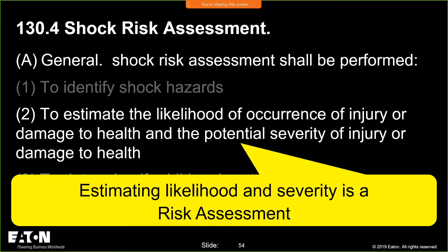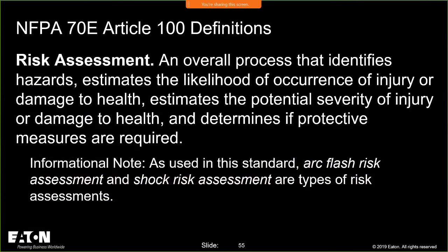A lot of people get the terms severity, likelihood, and elimination mixed up a little bit. But you have to establish and estimate the likelihood of occurrence that you're going to come in contact with these components. So you have to do a risk assessment, which basically estimates the likelihood of occurrence and injury, and the severity of that event. So you may say, I'm standing on a 2-foot step stool, and I could fall. I definitely could fall off of a 2-foot step stool. But the severity to me, if I fall off a 2-foot step stool, might not warrant putting on fall protection and doing all these other good things, because yeah, I could get hurt, but it's not going to be severe.